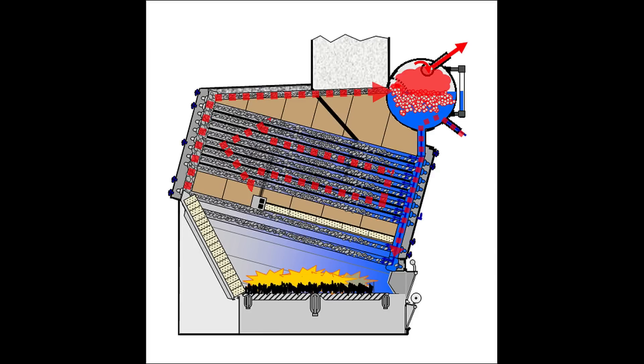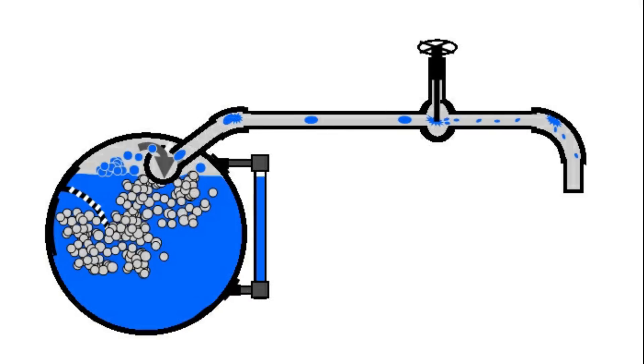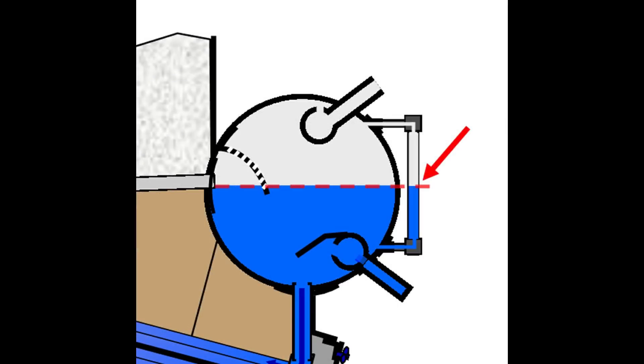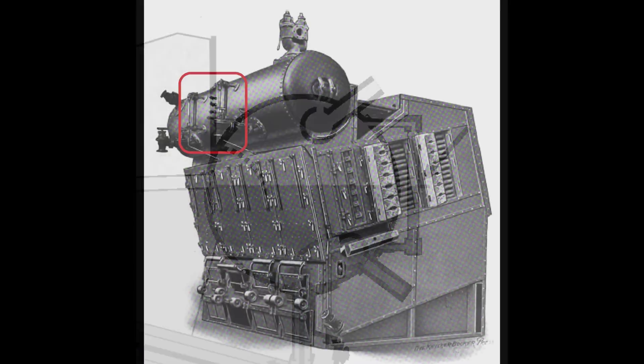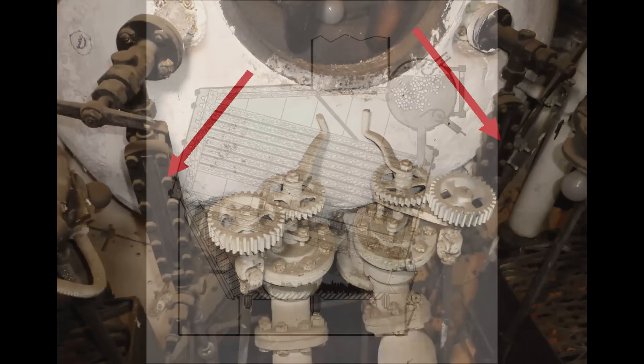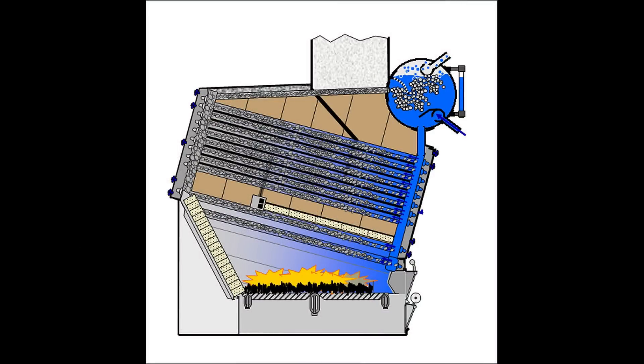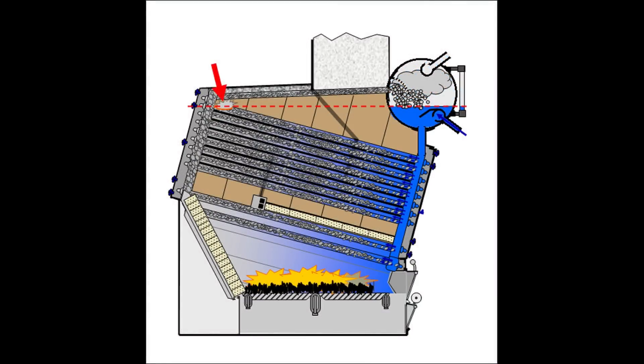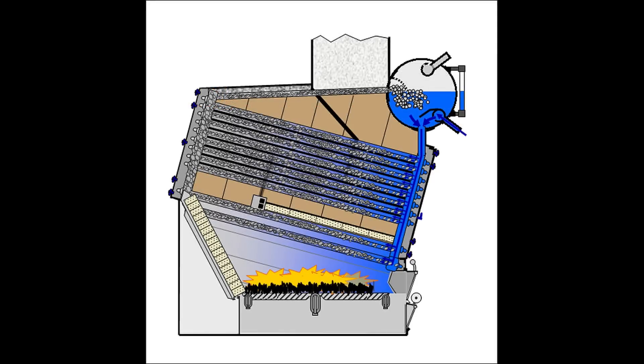Openings were located only in the top of the pipe for a very important reason. This greatly reduced water splashing into them since the pipe itself acted to block it. The goal was to reduce priming, which are slugs of liquid water entering the steam line. Think of priming as high-velocity water bullets that shot through the pipes and struck joints and entered equipment. It was to be avoided at all costs since it was extremely damaging. It was extremely important to control water level in the steam water drum, but hard to do since it could only be seen through small sight glasses. Levels could suddenly jump with engine speed changes and when other equipment was turned on and off. If too high, priming would occur that could damage pipes and equipment. If too low, tubes may be uncovered and melt. The water tender had to always be aware of water level, instantly know how to respond to a problem, predict what was about to happen, and even when to mistrust what he saw.